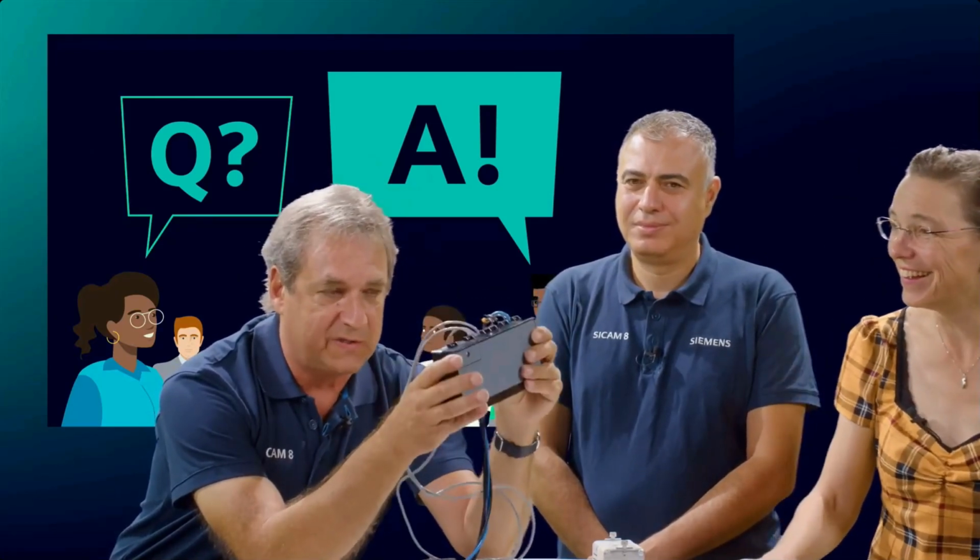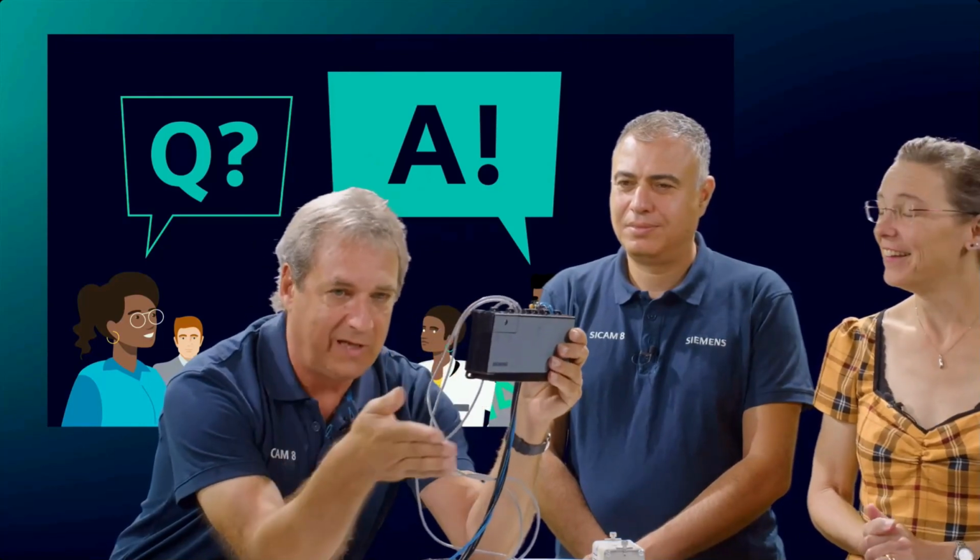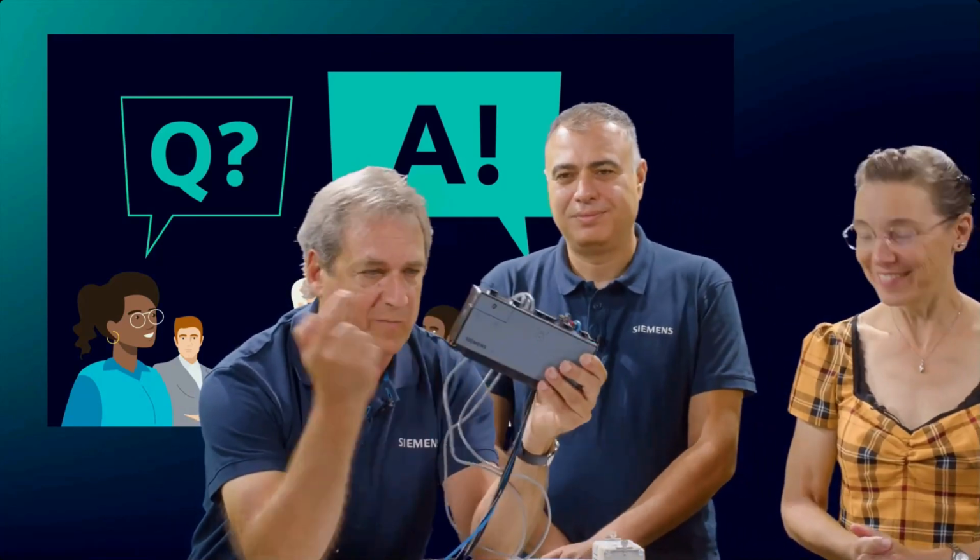Yes. Thanks. And why not a battery? Because I would have to exchange it. Very good question. Why not a battery? We want to reduce the maintenance and service activity of the customer. If we would install a battery inside, then maybe after 5 years, maybe after 10 years, all these devices have to be opened and replaced. That's what we want to avoid, and that's the reason why we have a capacitor inside.